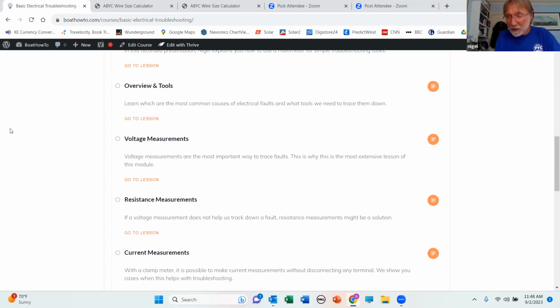So don't go buying some dipshit meter for $10. Get a decent meter and pay some money for it. And then if you want the amp clamp, which is a way of measuring amps safely as opposed to feeding them through the meter, basically you clamp that around the conductor and it measures amps. And there's no way you can get into trouble doing that. So that's a terrific piece of kit. The vast majority of amp clamps on the market only measure AC amps. So you want one that measures DC amps.